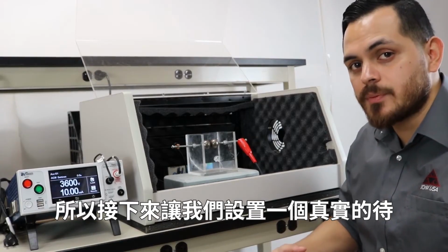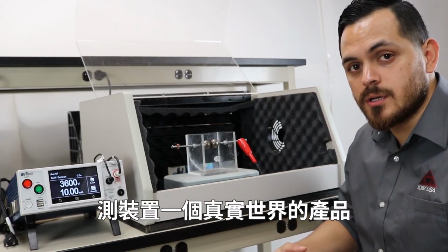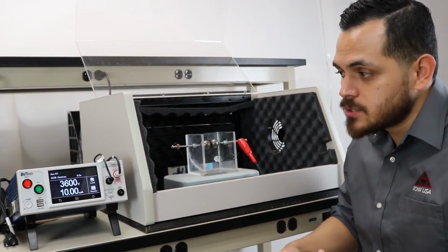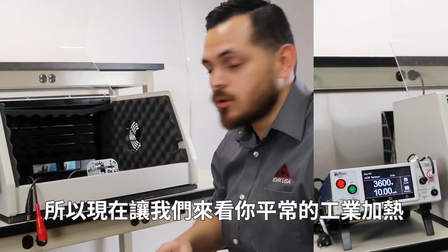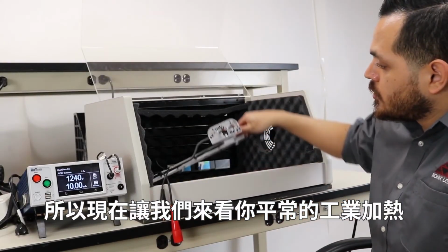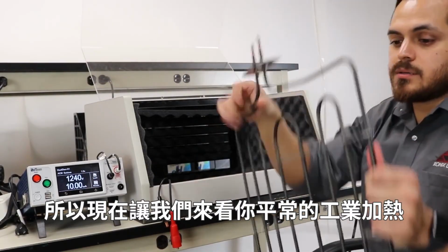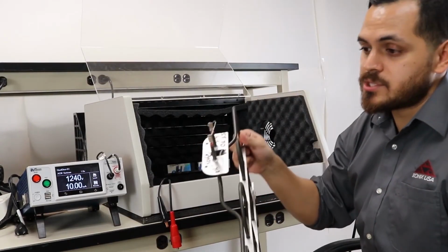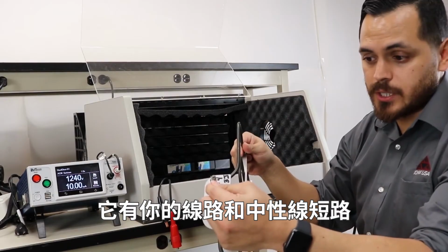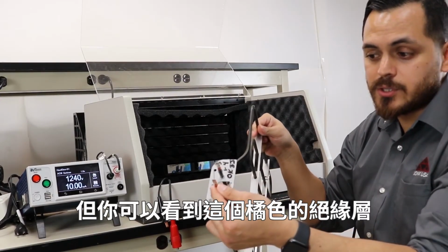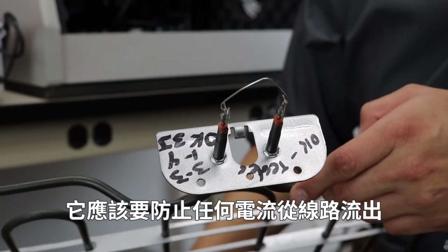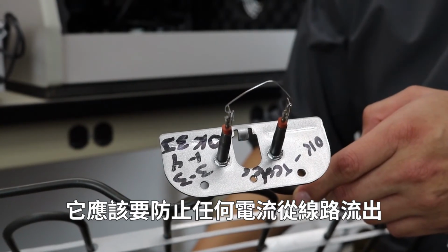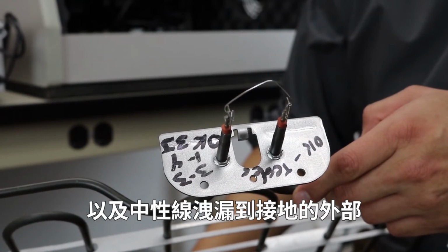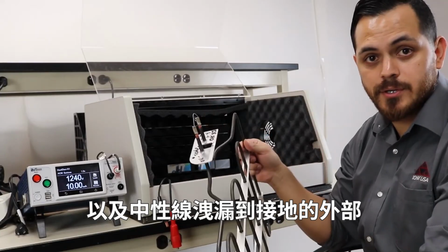So next, let's set up a real UUT, a real world product, to look at what type of leakage we're seeing. So now let's take your normal industry heating element, right, which has your line neutral shorted. Now we'll zoom in, but you can see this orange insulation that's meant to protect any current flowing through line and neutral from leaking onto the grounded exterior.